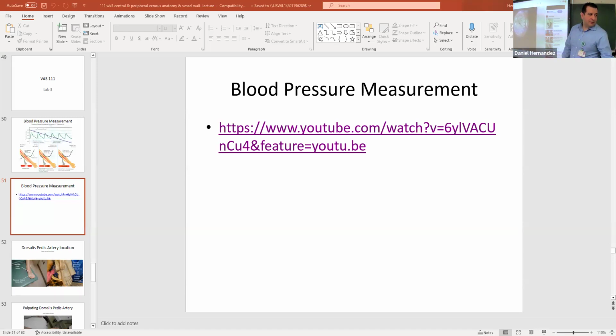This is the speed at which you should be releasing the air so that you can more accurately identify the first and last Korotkoff sounds. A slight adjustment of the valve is all you need to slowly release the air.